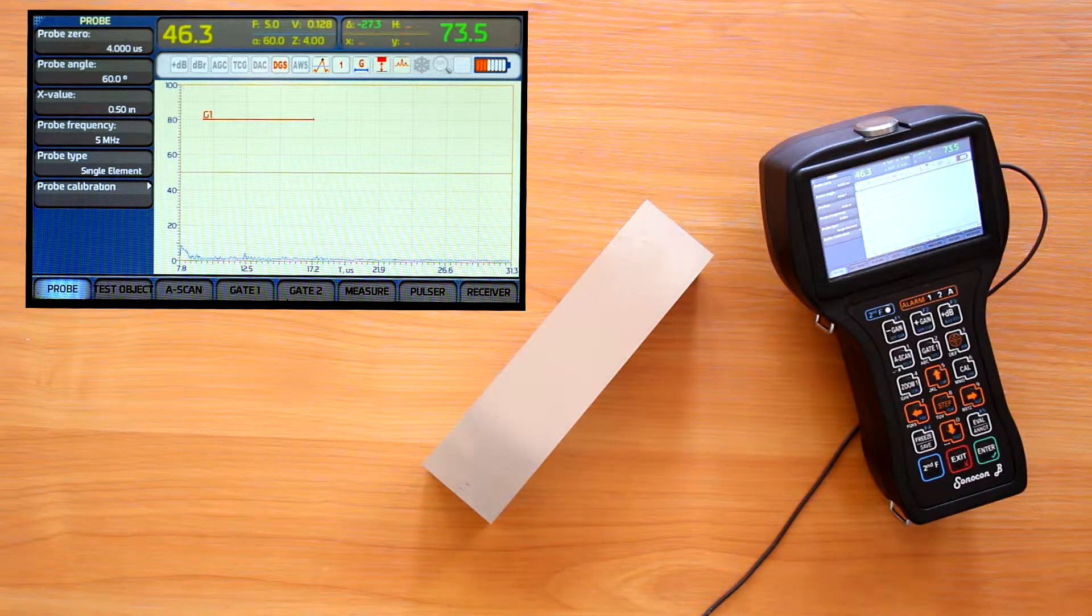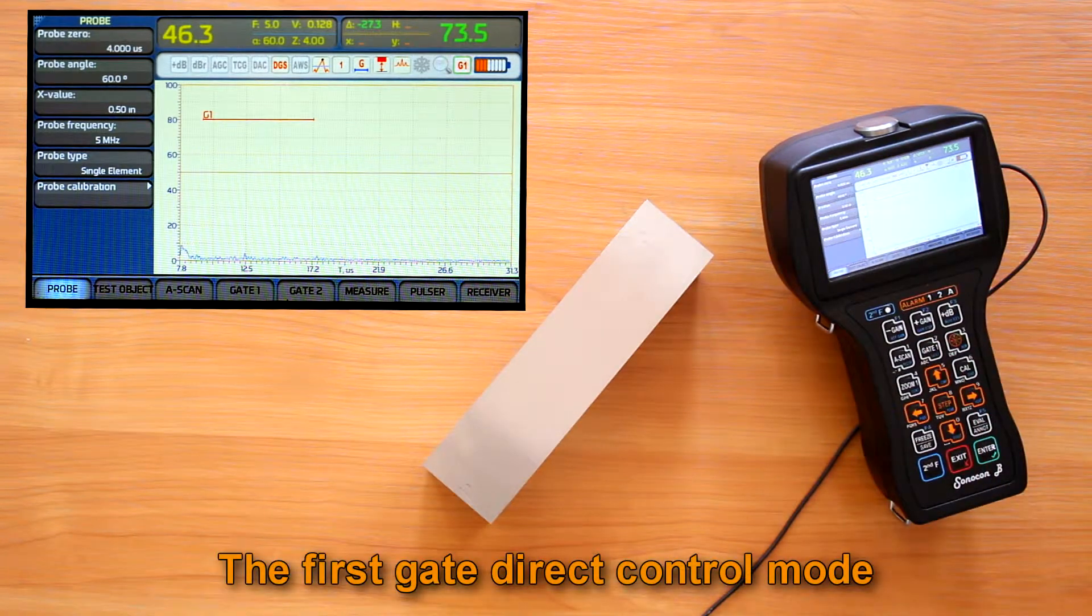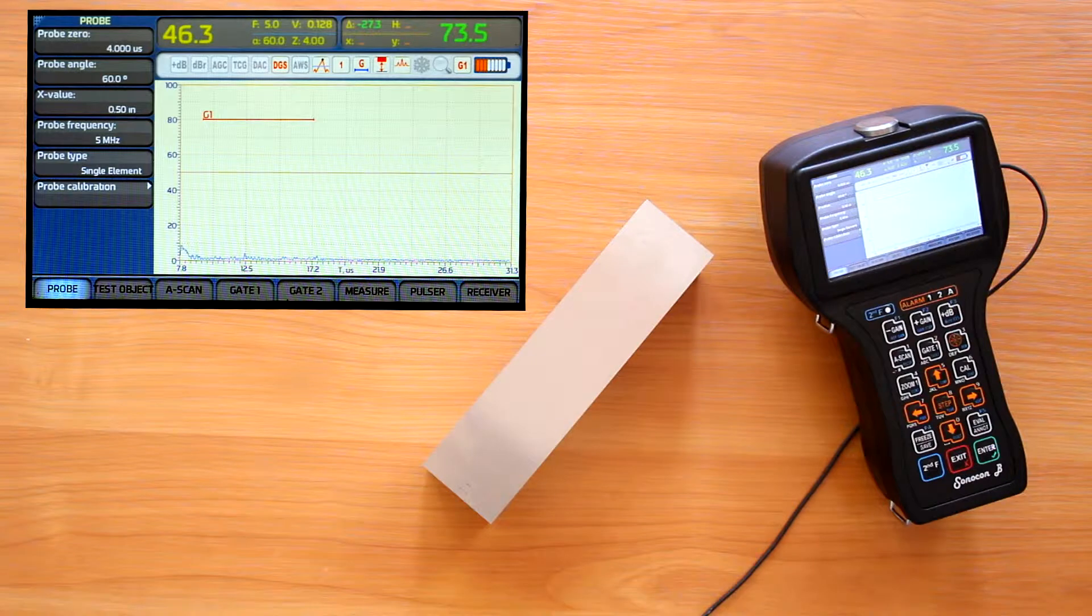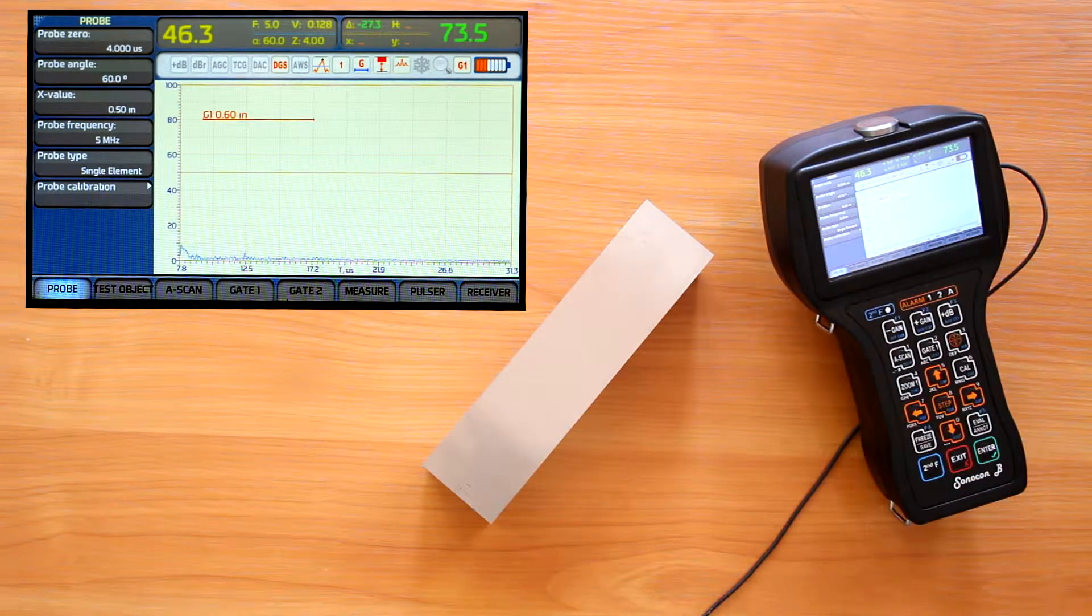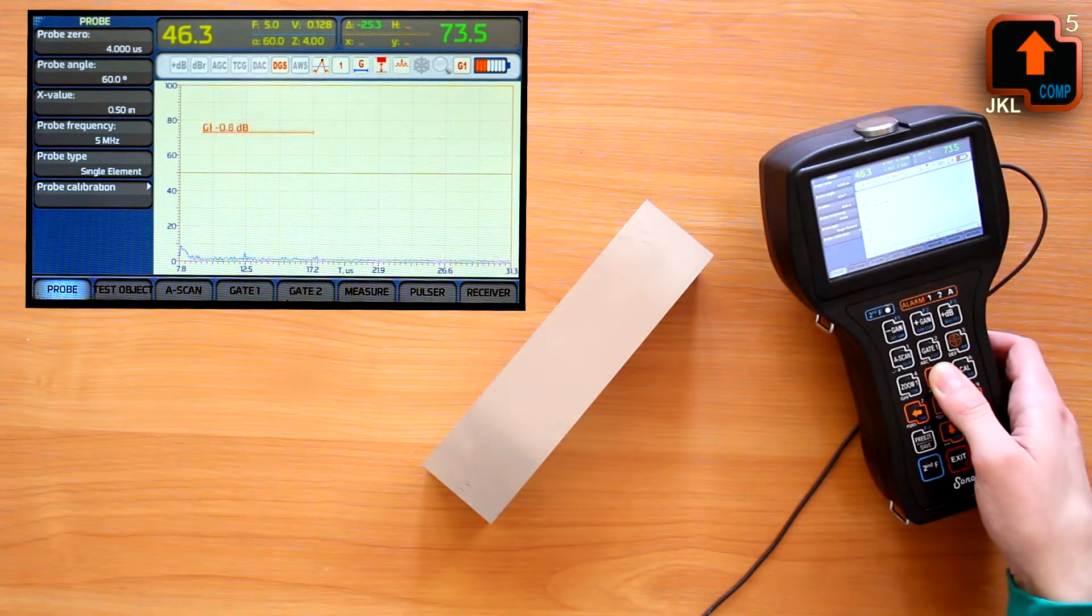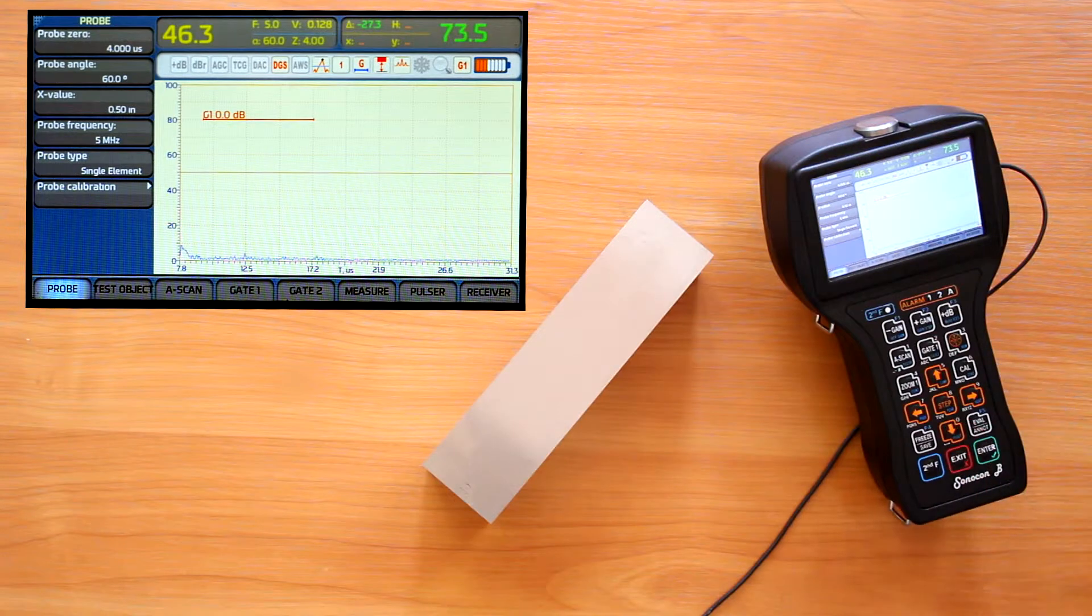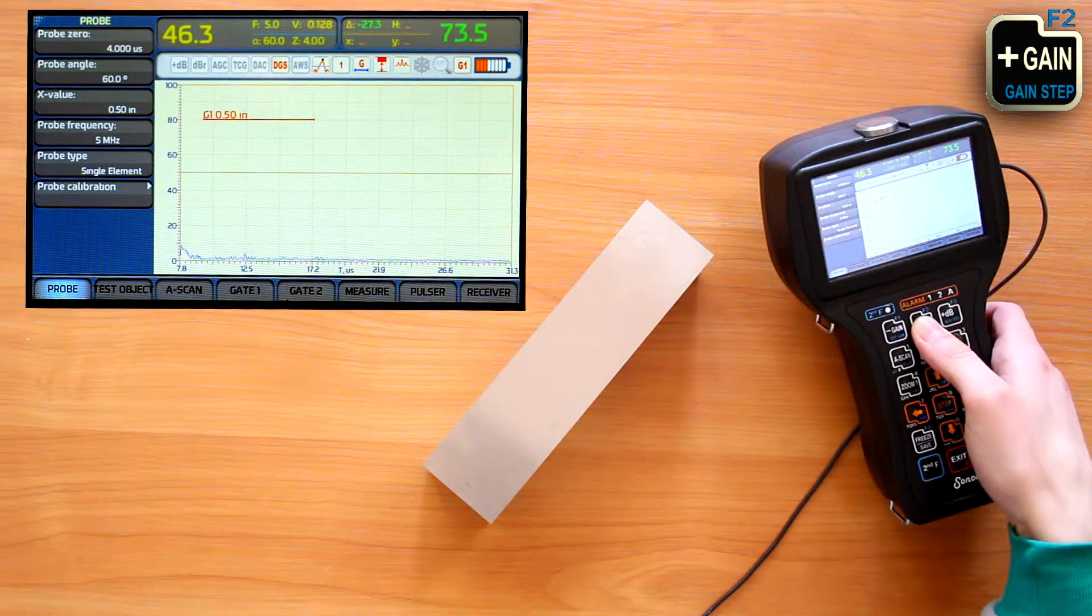Pressing gate 1 button, we enter the mode of the first gate direct control. The G1 indicator shows we are in this mode. Now we can move the gate right or left with right and left arrows. And up or down with up and down arrows. We can make it longer or shorter with gain plus and gain minus buttons.